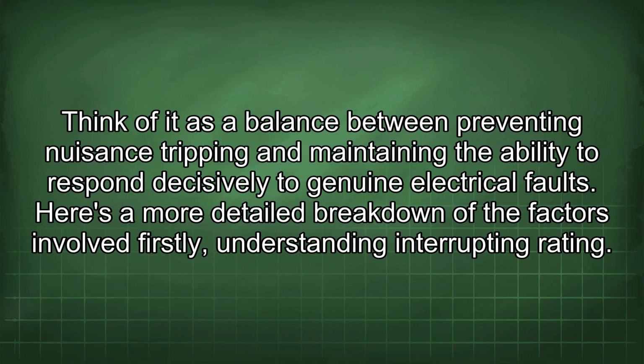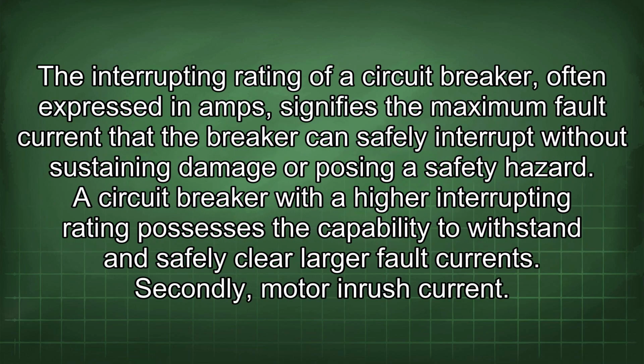Firstly, understanding interrupting rating. The interrupting rating of a circuit breaker, often expressed in amps, signifies the maximum fault current that the breaker can safely interrupt without sustaining damage or posing a safety hazard. A circuit breaker with a higher interrupting rating possesses the capability to withstand and safely clear larger fault currents.